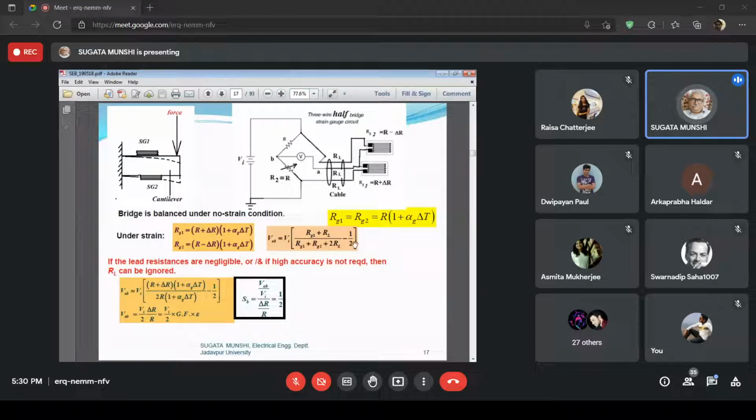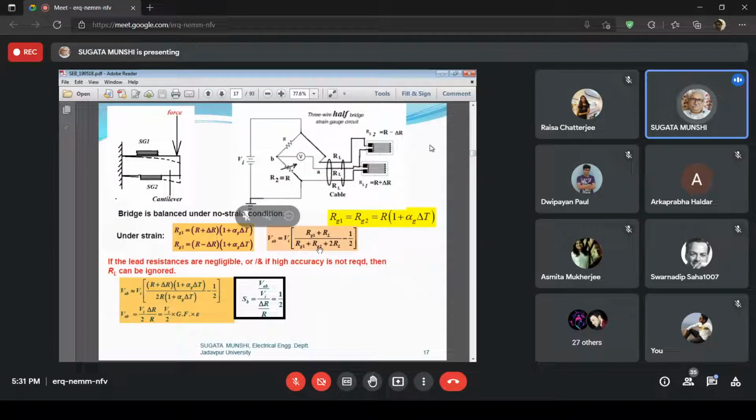So if the lead resistances are considerable, they are going to affect the measurement accuracy. Not only that, think about the situation that you are carrying out measurement over the entire day or for more than one day. So over that span of time, the resistance of the connecting leads, the cable cords, they will also change considerably. You cannot determine the change. You cannot monitor that change. But that is an infeasible method of calculating the resistance value of RL and then subtracting, etc.